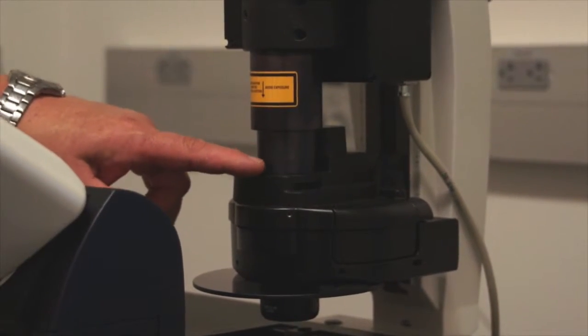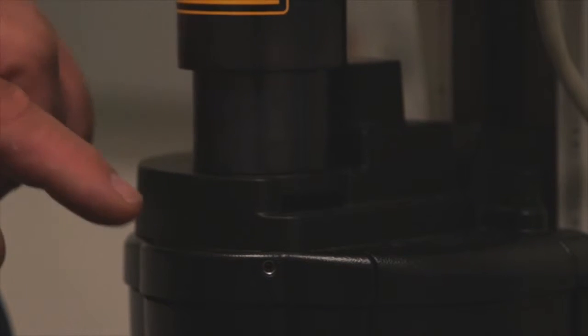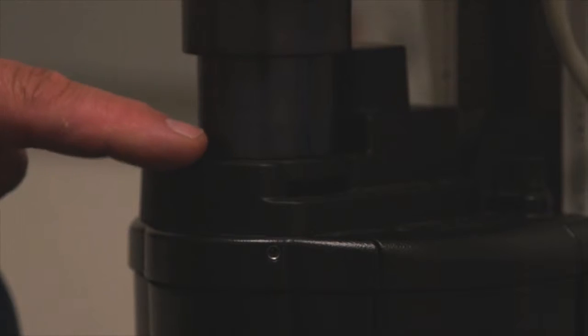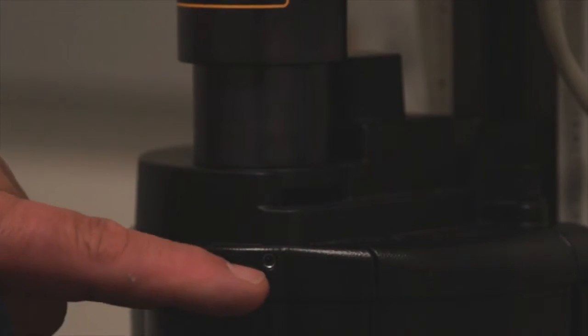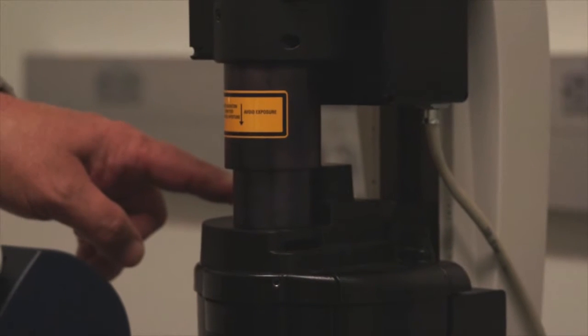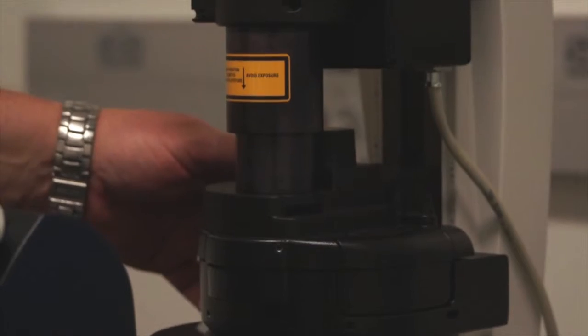Now the condenser does what we talked about previously. It condenses the light so that it goes into and through your specimen on the stage and into the optics. It is very, very important to align this condenser properly. And we will be showing you two alignment tools that go into these little slots to align the condenser in this plane. In addition, there's a knob on the other side of the condenser, which you'll see in a second, which allows you to raise and lower the condenser for correct positioning of the condenser.